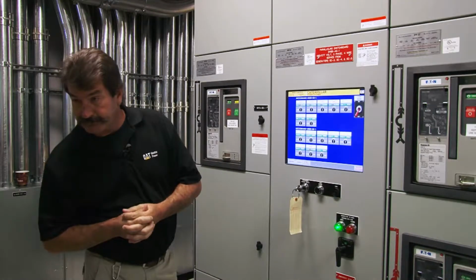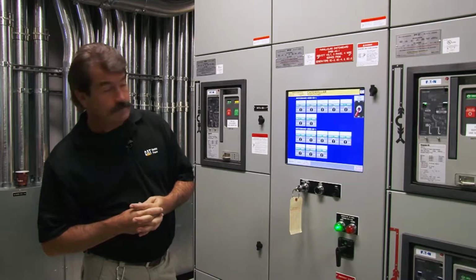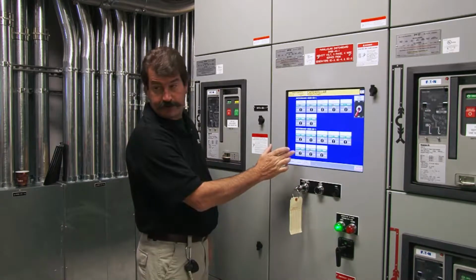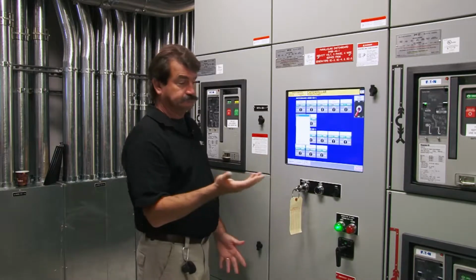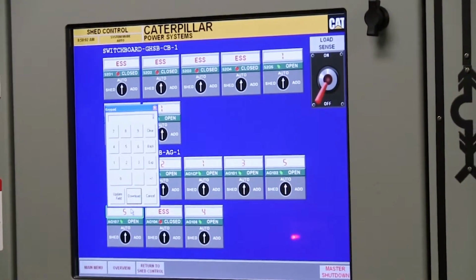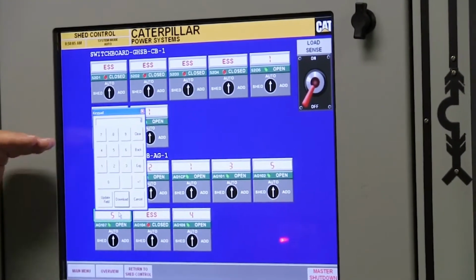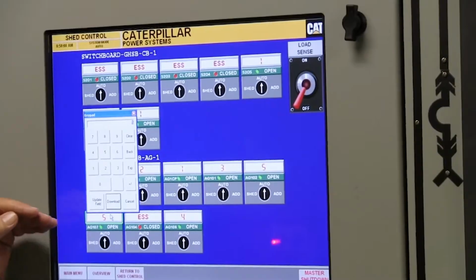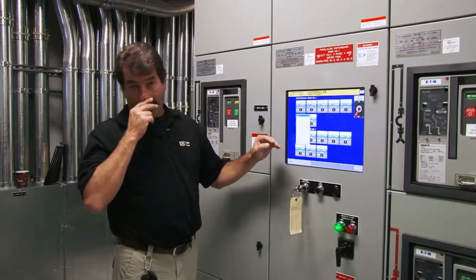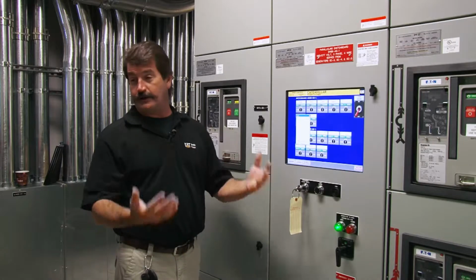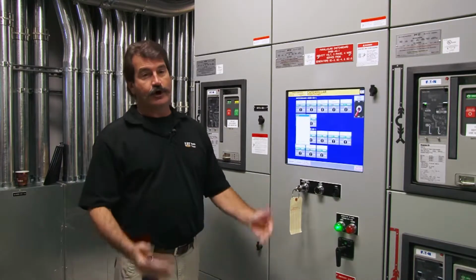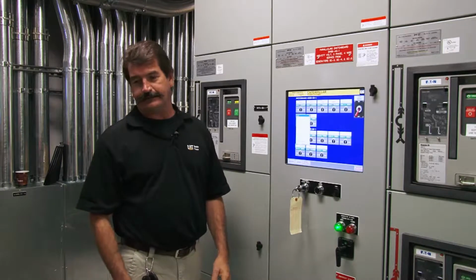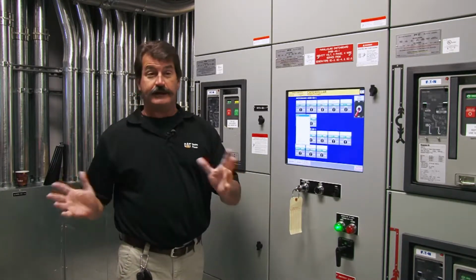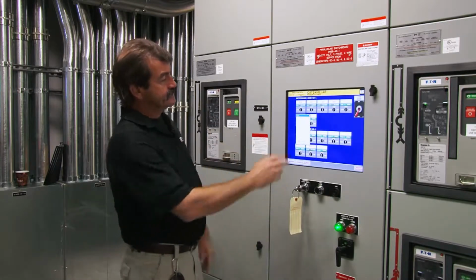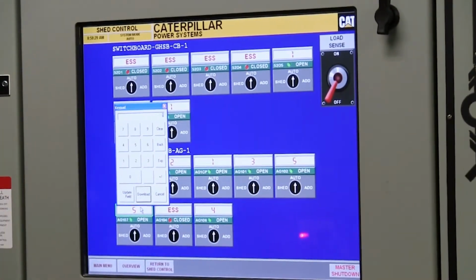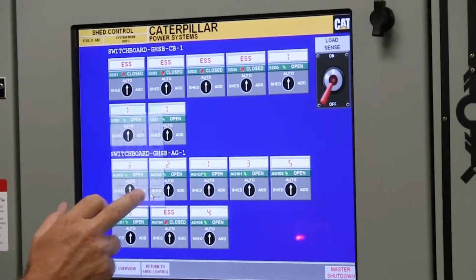How can you change which thing? The numbers are there. How can you change it? Just double tap this right here, okay? And once you double tap that window, then you can change it however you want to. Anything 5 or anything above 5 is going to be called non-essential. In which case, non-essential means that we will not try to close that breaker at all. We will open that breaker, but we will not try to close that breaker. Not really used in a system like y'all have here, okay? But you can change that from 5 to 2 to whatever, and then hit download, and you're good to go, okay?